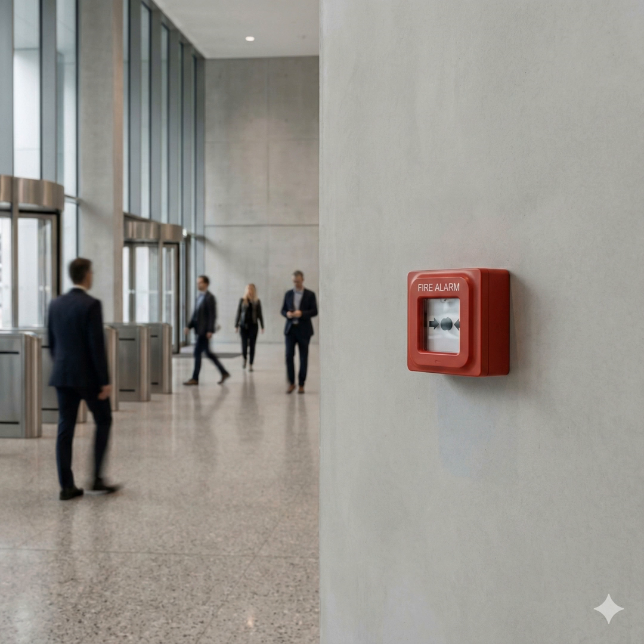Addressable systems, the modern standard, give a unique address to every single device. Every sensor, every horn, every module. And as we discussed earlier, that's crucial for faster response. But how does that unique address help the maintenance crews? Think about troubleshooting a fault. In a conventional system, you get a ground fault signal, you know it's in zone 5, but you have to physically search every wire and junction box in that area. Which could take hours. Or days.